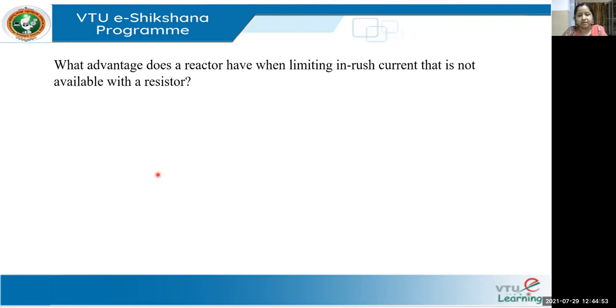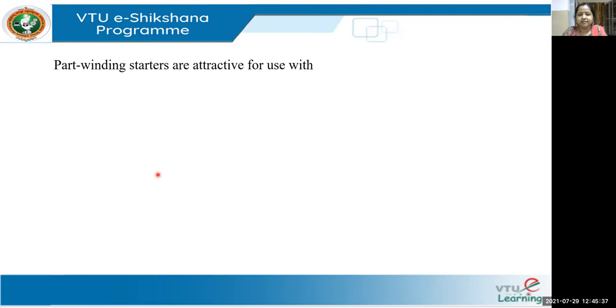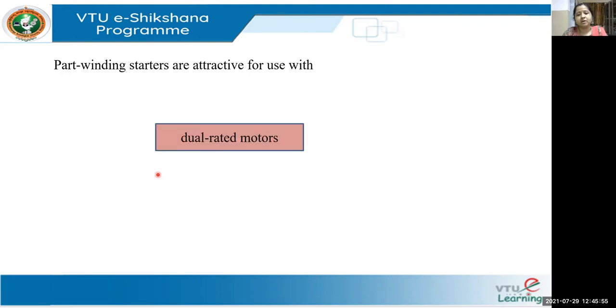Question 3: What advantage does a reactor have when limiting inrush current that is not available with a resistor? The answer is the rise time of current. In a resistor starter, current rises instantaneously, whereas in a reactor starter, the current rises at an exponential rate. Question 4: Part winding starters are attractive for use with dual rated motors — these are motors with two ratings, also called dual rated motors.